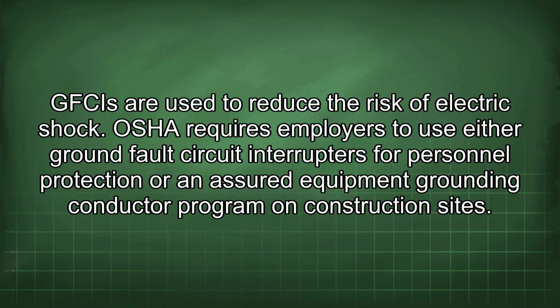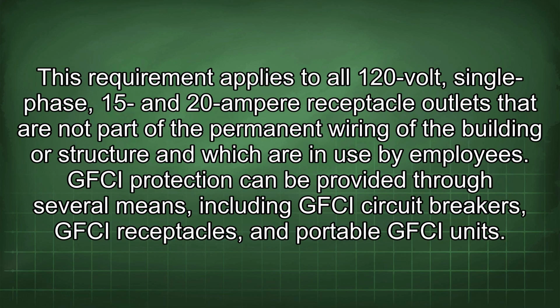OSHA requires employers to use either ground fault circuit interrupters for personnel protection or an assured equipment grounding conductor program on construction sites. This requirement applies to all 120-volt, single-phase, 15 and 20 ampere receptacle outlets that are not part of the permanent wiring of the building or structure and which are in use by employees.